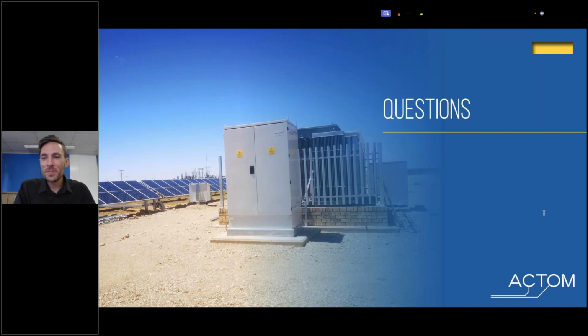Rutent Mufamad asks, in the near future do you have any devices that help with harmonics? In terms of harmonics, it's more a design parameter, and you've got CT lab instruments for power quality that measure that. Power quality devices normally measure harmonics, but currently we don't have a requirement to measure that ourselves. If it's needed for a specific client, we're working with the Vector 3 and newly launched meters, so it's something we can look at.